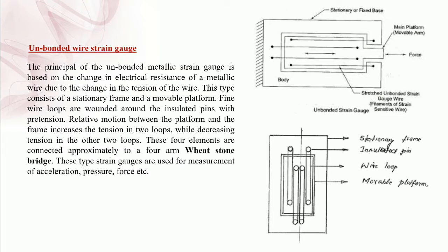And these unbonded wire strain gauges are usually operated on input potential ranging up to 35 volt direct or alternating current. Under conditions of extreme unbalance corresponding to full operating range, the open circuit EMF may be of the order of 8 to 10 millivolt, and the closed circuit current up to 100 milliampere. Strain gauges are basically used on AC circuits which are supplied in both capacitive and inductive forms, wherein corresponding characteristics of AC circuit components are varied by the displacement to be measured.